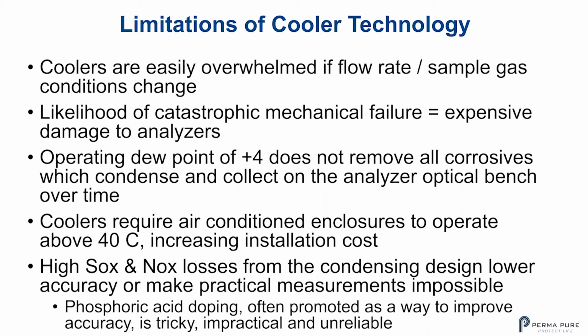So coolers fail, like a lot of electromechanical devices. When they fail, they will fail catastrophically. That's just normal for that type of equipment. It's just what it does. You also have an operating dew point of +4, which is what they cool to. It does not remove all the corrosives, which can condense and collect on the analyzer optical bench over time.